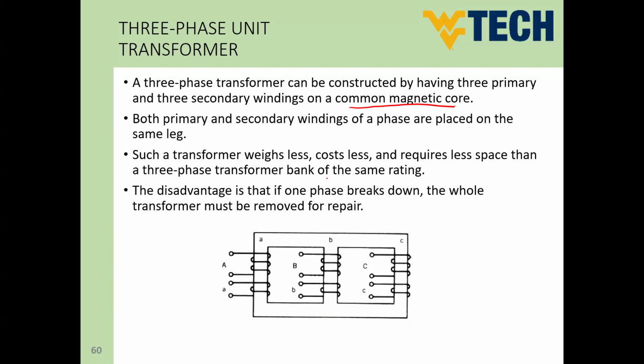If this is more beneficial, why do we still need to use three single-phase transformers? Everything, guys, has advantages and disadvantages. So let's see what the disadvantage of this one is. The disadvantage is that if one phase breaks down, the whole transformer must be removed for repair. This is the drawback compared to the three single-phase one.